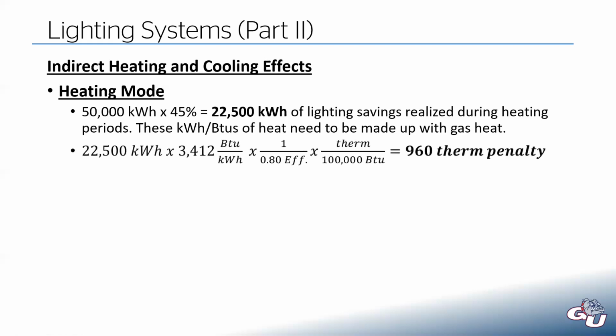So if you run through a calculation, we convert the kilowatt hours saved, so that's the heat load reduction, to BTUs. We would always divide by our efficiency, because remember, we pay the utility in terms of input. So if our heating system is going to output this amount of energy, we have to divide by our efficiency to arrive at an input, because that's what we pay the utility. Utilities often bill in terms of therms. And so this ends up being a 960 therm heating penalty. So now we have to use more gas than we were using before.